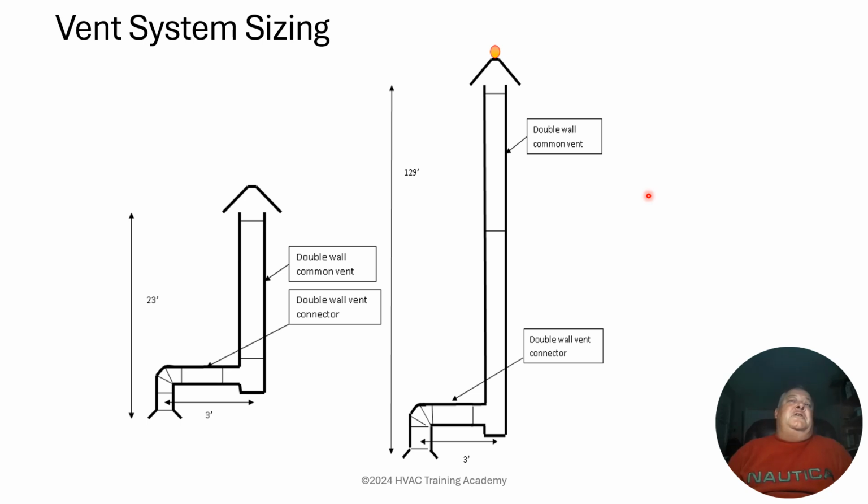Extrapolation is going to be, let's say our table ends at a 50-foot vent height, for instance, and we have a 60-foot vent system, and we said, well, mathematically, we could go in and calculate the difference based on the table values that are already in the table. We could go ahead and calculate what 60 feet would be equivalent to. Because the table has ended, that is the outermost parameter is 50 feet. Extrapolation is known as basically going beyond the table values.